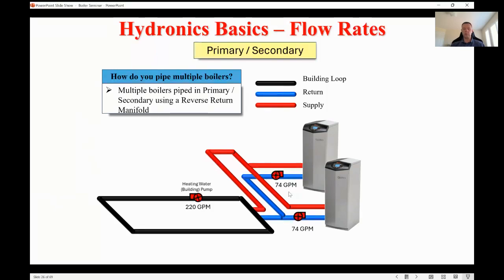The last one in is the first one out. So it's a reverse return situation in there. So it's self-balancing. Each boiler should get the exact same amount of flow because they're pumping through the exact same amount of piping. And of course, each one sees the same return water temperature. So they're all operating at maximum efficiency. It's not like in series, where each unit would see a higher water temperature and be a little bit less efficient. Generally, if you pipe your multi-boiler low mass products like this, as long as you've sized your pipes and your pumps right, you shouldn't have any flow related issues with low mass appliances.